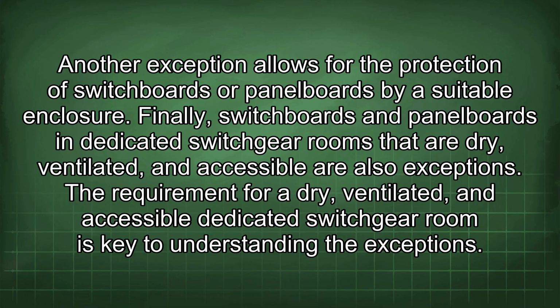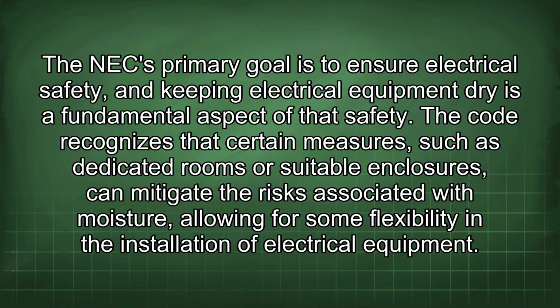The requirement for a dry, ventilated, and accessible dedicated switchgear room is key to understanding the exceptions. The NEC's primary goal is to ensure electrical safety, and keeping electrical equipment dry is a fundamental aspect of that safety. The code recognizes that certain measures, such as dedicated rooms or suitable enclosures, can mitigate the risks associated with moisture, allowing for some flexibility in the installation of electrical equipment.